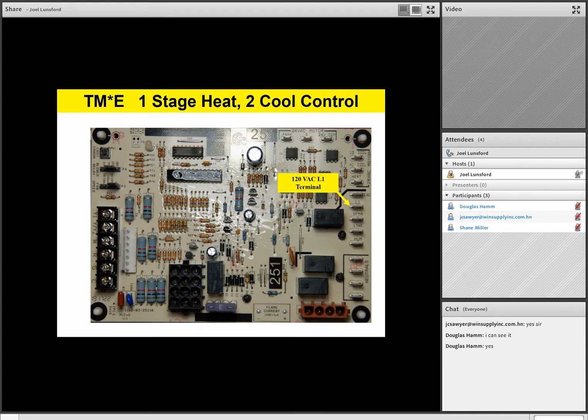Right below that terminal we have what we call an XFMR terminal. That XFMR terminal is for a transformer. That's the 120-volt line voltage for the transformer. Now right below that, there's another terminal called line, L-I-N-E. That line terminal goes to the ECM motor, because remember we mentioned that anytime you power up an ECM product, the furnace is powered up all the time. It has line voltage to it all the time, but the motor's just sitting there doing nothing.